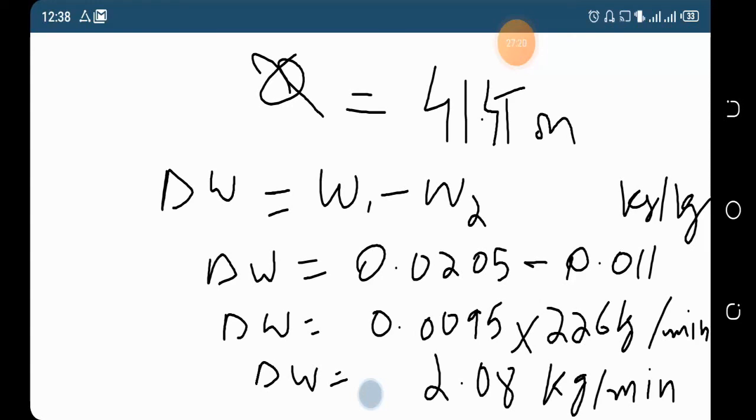You can find the sensible load of the human body from the ASHRAE book, and you can also calculate the sensible and latent heat of a person, multiply by the number of persons, and add them. The values come in kilowatt. Then convert this kilowatt into tonnage, and you get to know the required capacity of chiller to be installed.